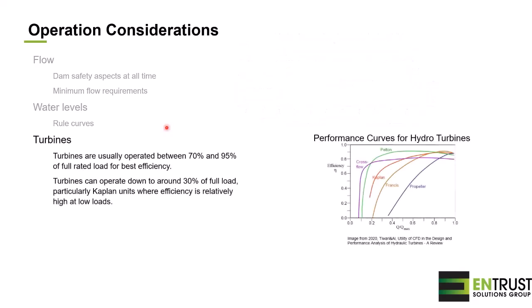We will also operate the turbines to make sure that we have the best efficiency. Ideally, we want to operate as much as possible close to 95% at all times, but it's not always possible, depending on the type of turbine that we have, and also the number of turbines that we have in a plant. So we will have to check what is the best efficiency for the whole project.